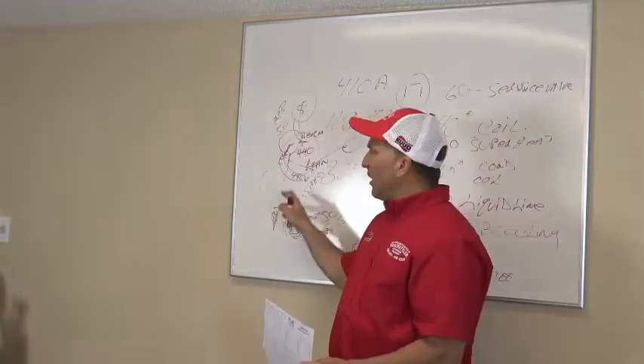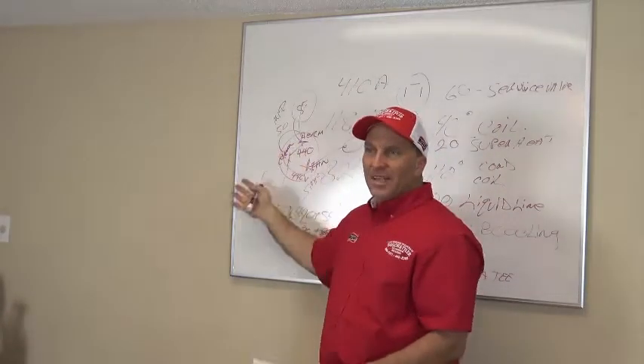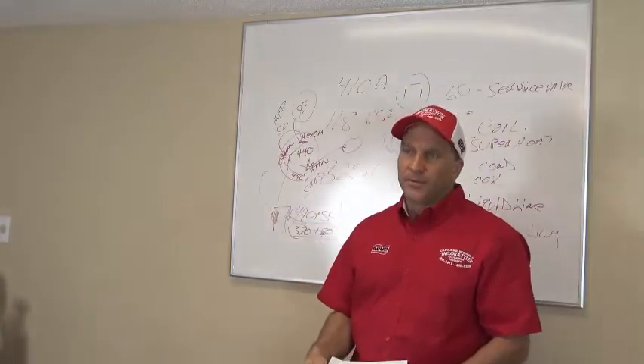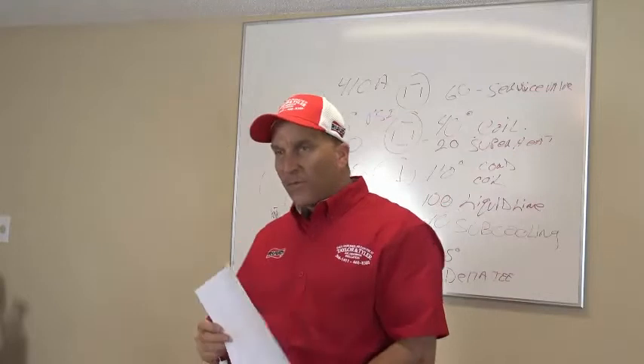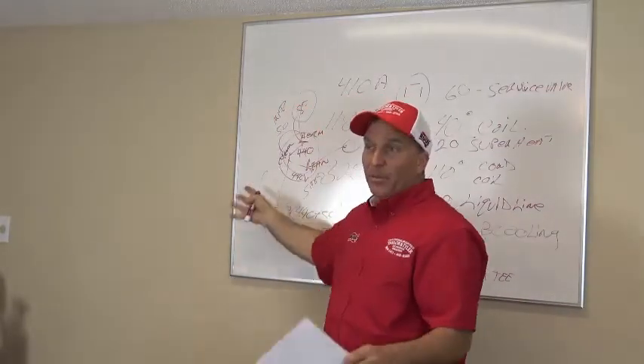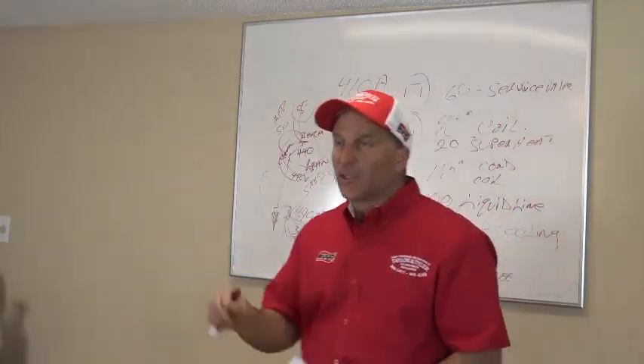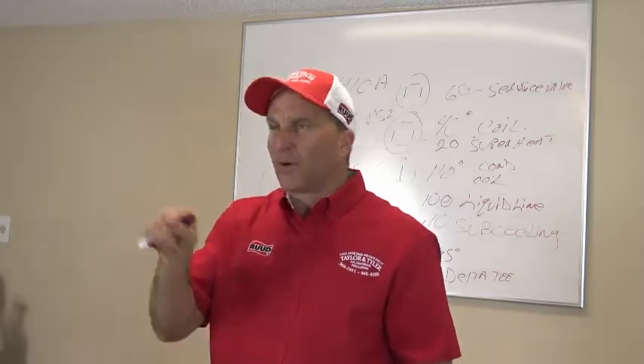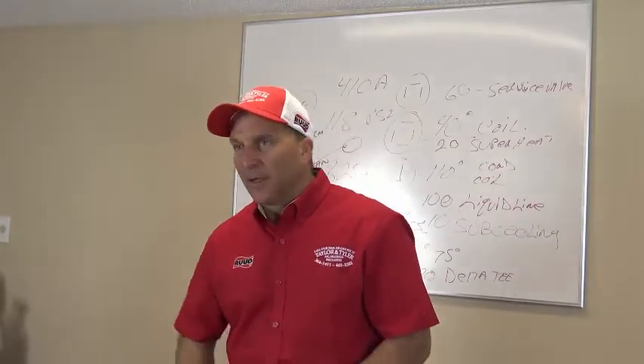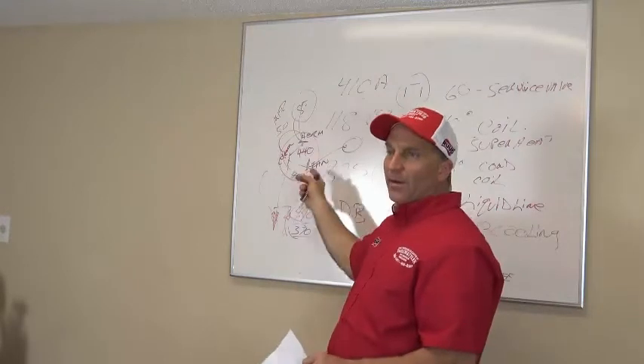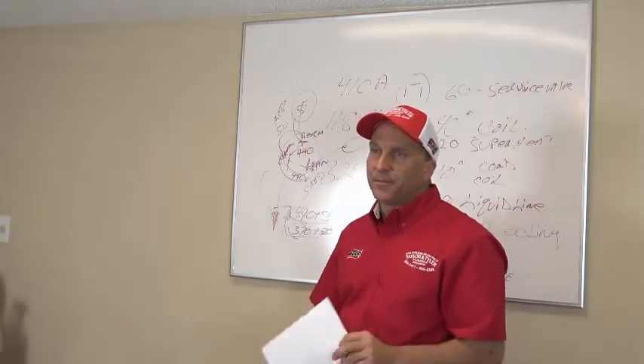What if there's liquid on top of the capacitor? It's leaking. Okay? It's leaking. What if your terminals are burned on it? You got to replace it, right? You can't just fix the wire and put it back on that burnt terminal. You got to replace it. And you got to fix your wire. If you don't fix the wire, it's going to burn it right back again. Okay.